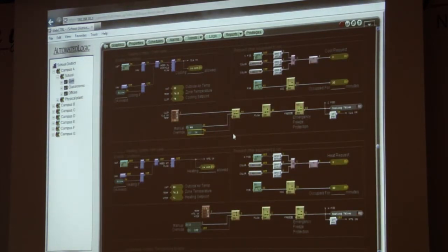The reason why we did this manual override, remember I just told you about those freeze conditions? Notice how if you use the manual override here, we still have to prove flow of the unit, so we'll make sure that we have flow. And then the freeze protection could still kick in, all right? You can still lock the output, we just need you guys to know that locking outputs is dangerous if you're not staying focused on the air handler. You could trip a freeze stat because you're keeping the valves closed, the hot water valve is shut, and the unit's cooling down, and you just forget about it, whatever the case may be. So we put this in here to try to keep that unit running.